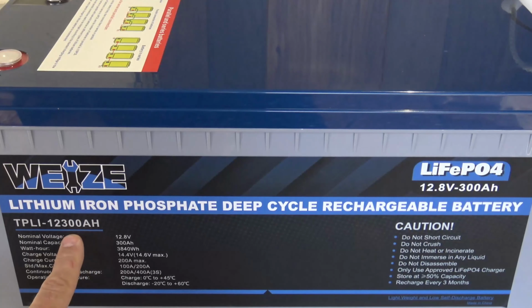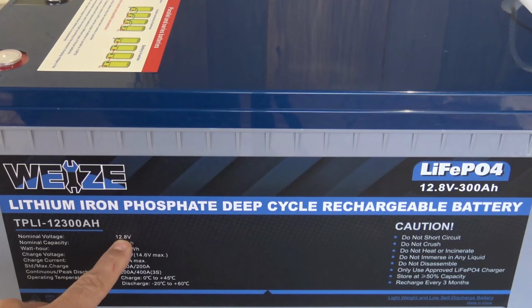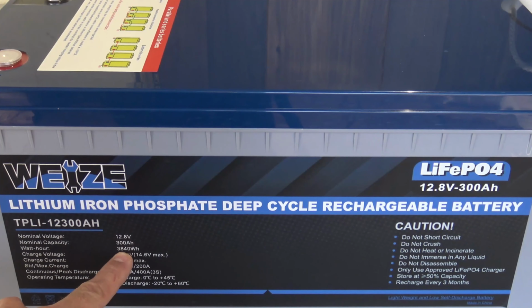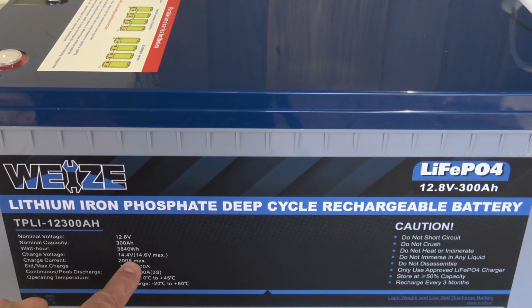It gives you some information here. Nominal voltage is 12.8 volts. The capacity is 300 amp hour, and that capacity in watt hours is 3,840 watt hours. Charging voltage is between 14.4 and 14.6 volt DC, that's the max. Charge current up to 200 amps maximum.